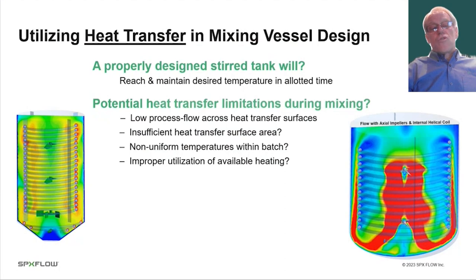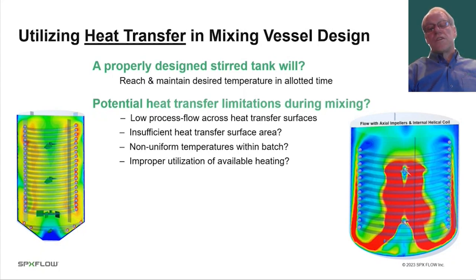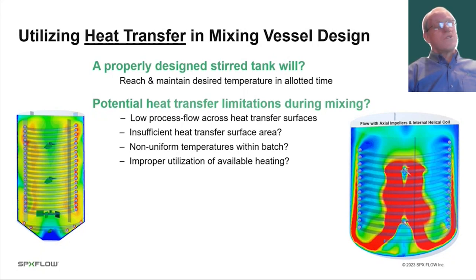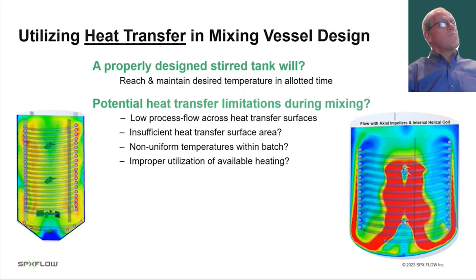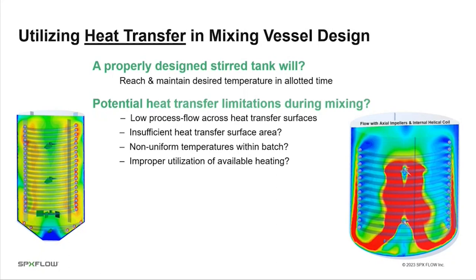A properly designed mixing vessel will successfully utilize heat transfer to reach a desired temperature within an allotted time. There are potential limitations — for example, low process flow across the heat transfer surface, inadequate surface area, non-uniform temperatures within the batch due to poor mixing, missing zones, or not fully utilizing the available heat transfer. Issues can also arise from the way heat transfer areas affect fluid flow.